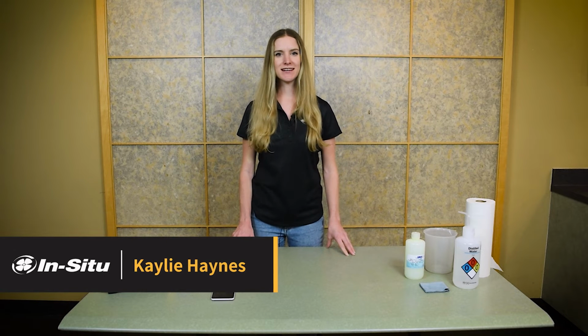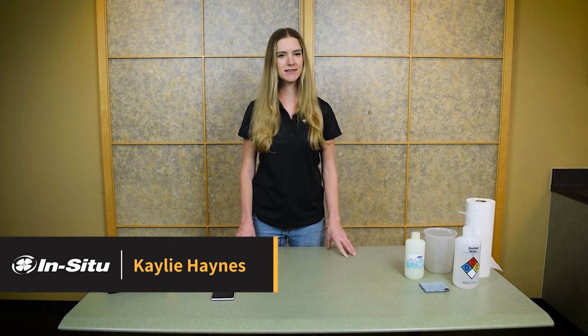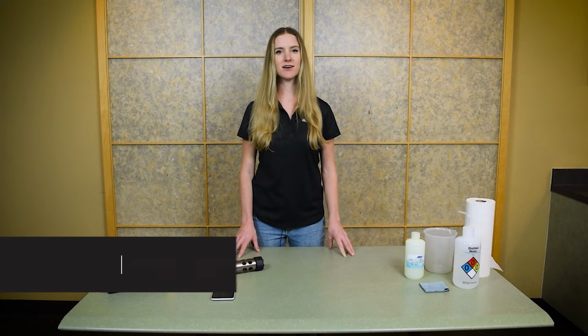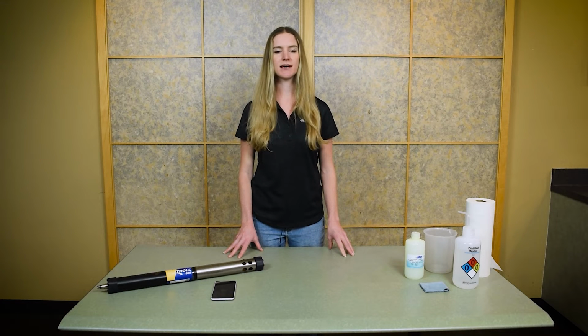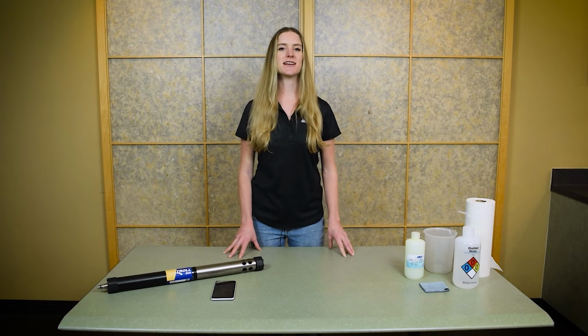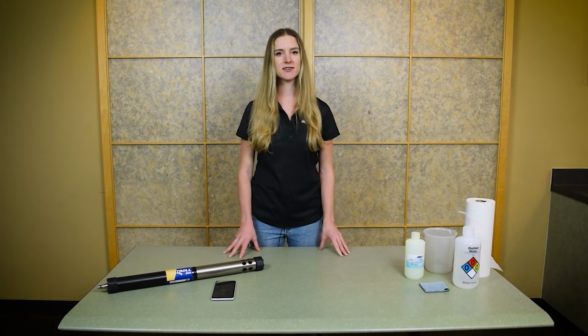Today I'll be showing you how to clean and calibrate your turbidity sensor. In-Situ's turbidity sensors offer high accuracy over the lifetime of the sensor when properly cleaned and maintained. We recommend sending your sensor in for factory maintenance once a year, and our service team will maintain, test, and calibrate your sensor for you.